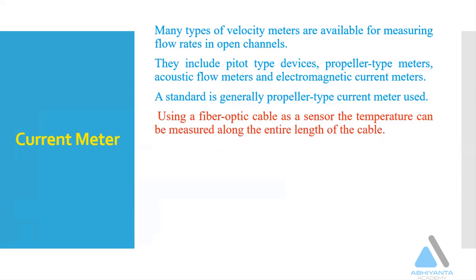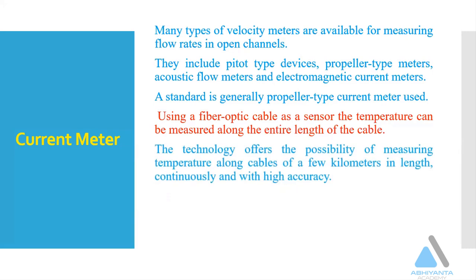Now this is the most important one. Using a fiber optic cable as a sensor, the temperature can be measured along the entire length of the cable. The technology offers the possibility of measuring temperature along cables for a few kilometers continuously and with high accuracy. This is installed inside a dam body as well.